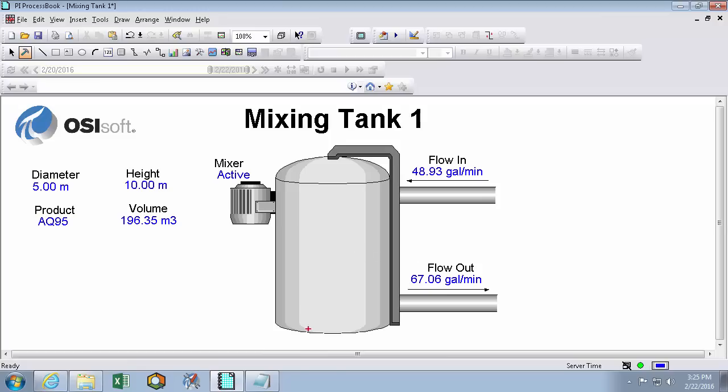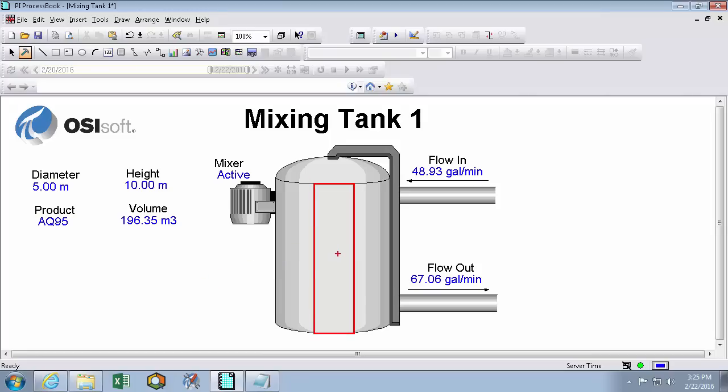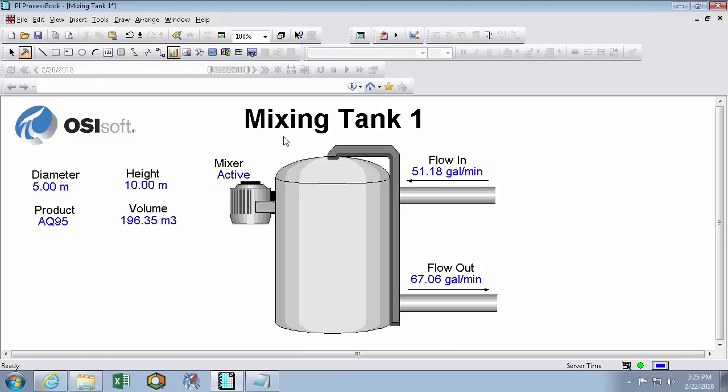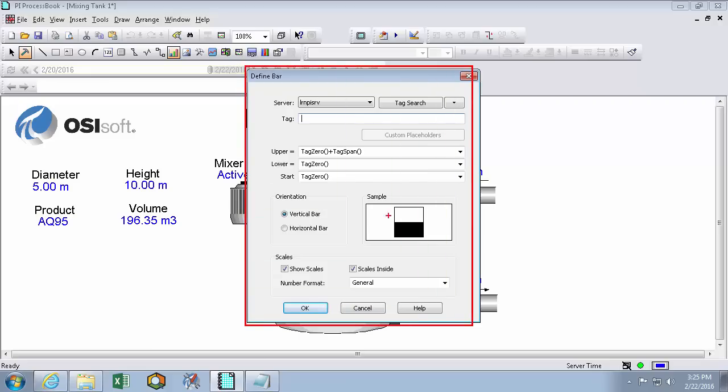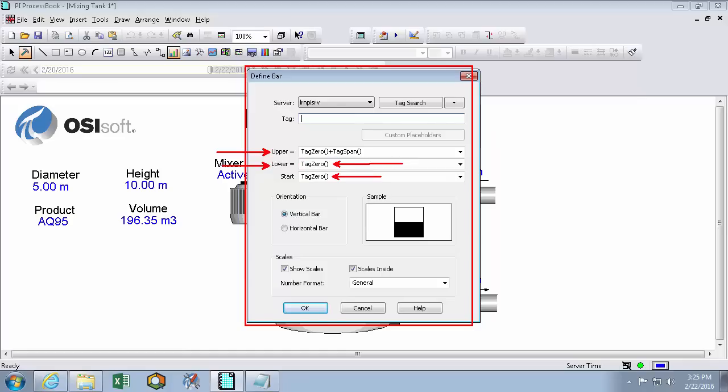Alright. So now we can add a symbol that'll really give us a good example of how much fluid is actually in the tank. And that's going to be a bar graph. And if we arrange it properly, it might actually look like our tank's cut away and we can see into it and see exactly how much fluid is in it. So we'll make a bar graph and we'll put it right here. And now this definition window is a little bit more complicated because the bar graph needs to know what the lower value of the bar graph is, what the upper value of the bar graph is, and if you want the fluid to start at the bottom and go to the top, or start at the middle and go up and down, or start at the top and go down.